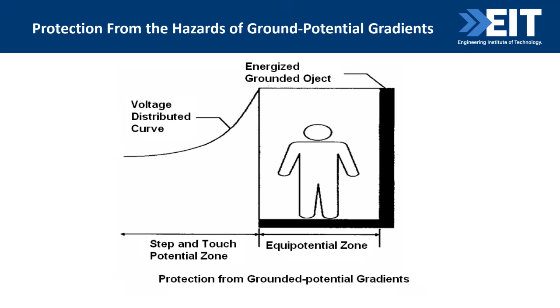Now there's two types of conductors, bonding conductors and earth electrodes. I'm not going to go into earthing in detail, but I've got quite a few slides here to do with earthing because it's a particular area of interest to me. But bonding is when you tie two conductors together, and earthing is when you connect a stake that goes into the ground.